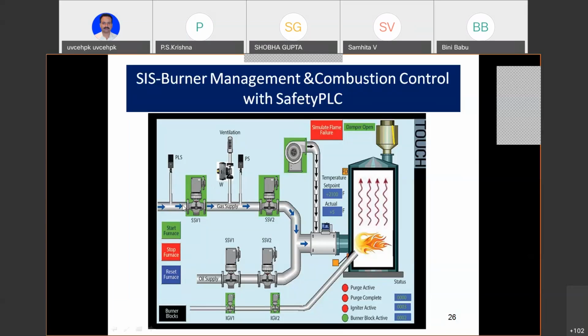Now, coming back to this: you've got a low pressure switch, a shutdown valve, and another shutdown valve. We are talking about gas, and then this path goes here. Let us go to the oil. Oil has the same: shutdown valve 1, shutdown valve 2. Why? Redundancy. If one fails, the other one takes over. Suppose this fails to close, then you have the other. So you've got 2. Then you will ask me, what is this in between?